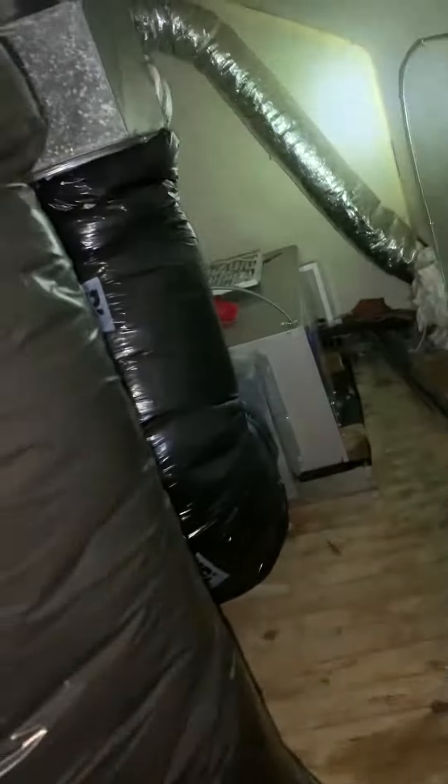Taking a look in the third-floor closet — this back here is our second-floor unit. There is a return down there on the second floor; I don't know how it's making its way back to this unit. The filter is totally blocked down there, so it must be sucking from somewhere, but there's nothing attached to the back side of that return and nothing on the bottom.